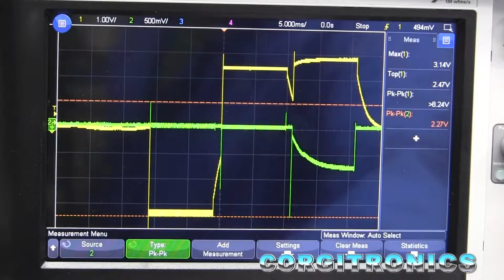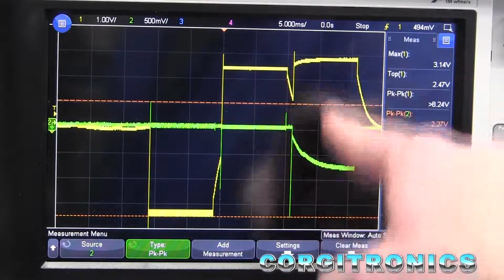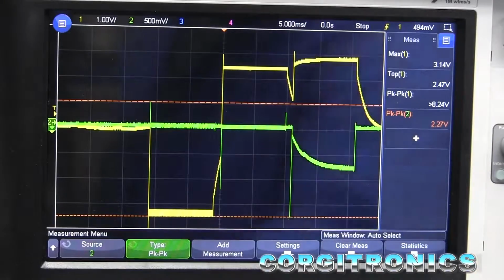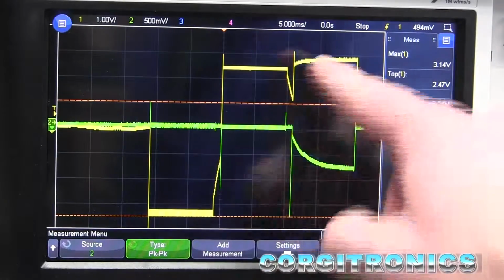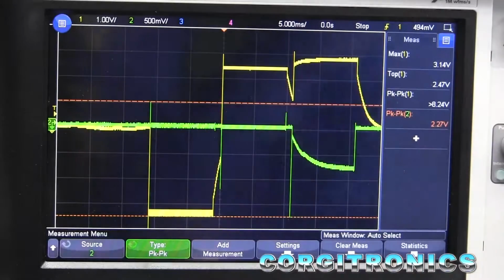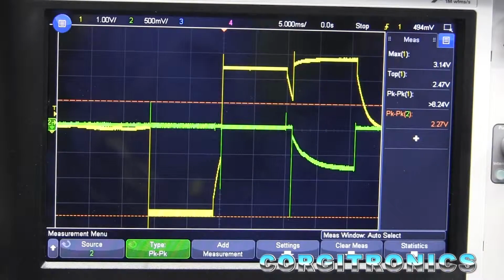On channel 2 we're at 500 millivolts, so we're looking at about 17.5 milliamps right here in this pulse. That's pretty good size considering we had it set to 10, but it's a stunningly short pulse.